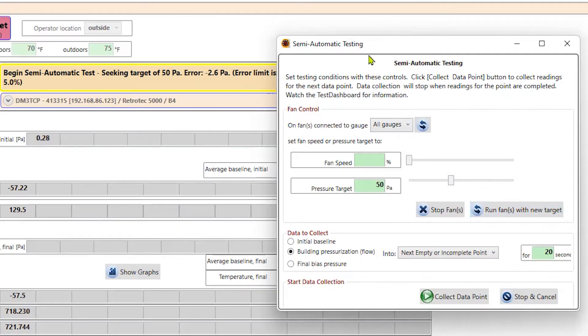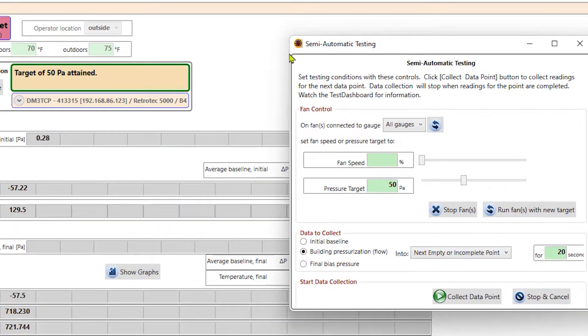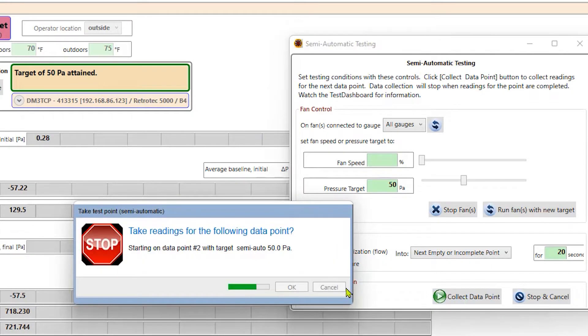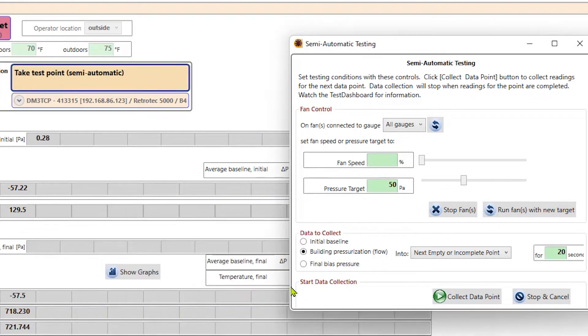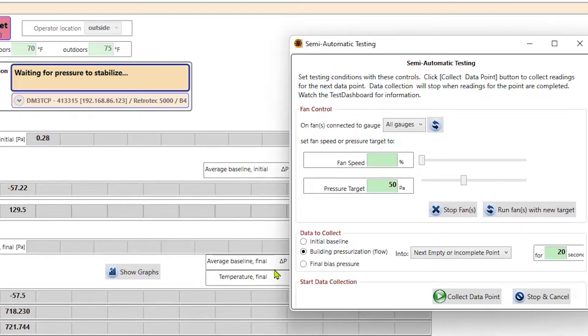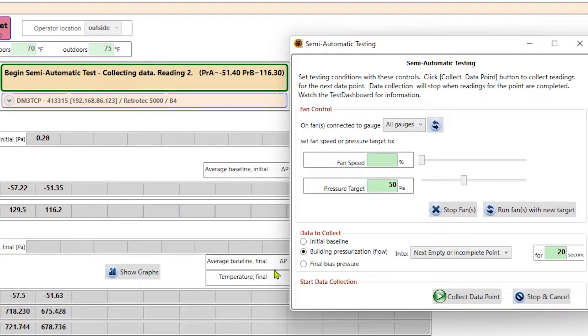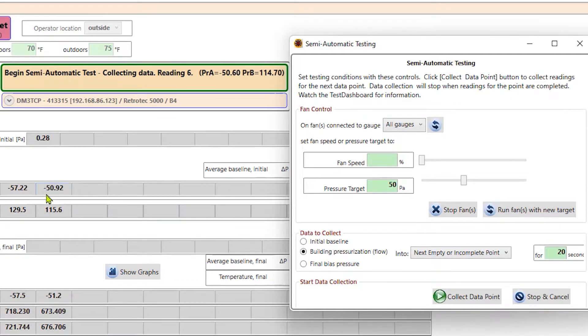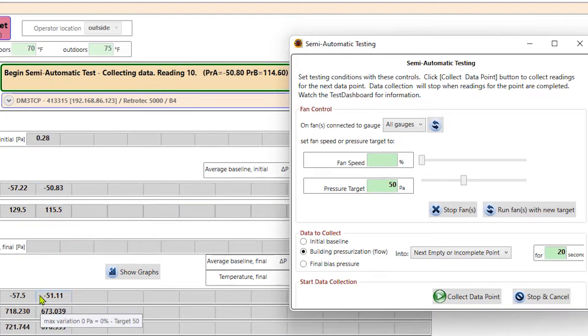And then we can say run fans to new target. Now we can hear that fan start to decrease speed as it seeks 50 Pascals. And then we're going to look at this window. There we go. It turns green and says 50 has been attained. Now we can collect data. So we'll do that. And then it will collect data for 20 seconds at 50 Pascals. And we can see that information start to be collected here and the second row under building pressure.